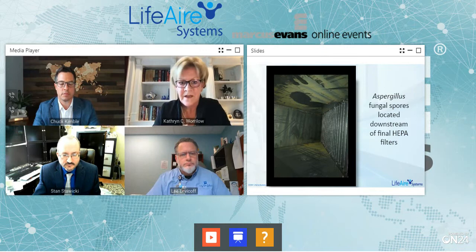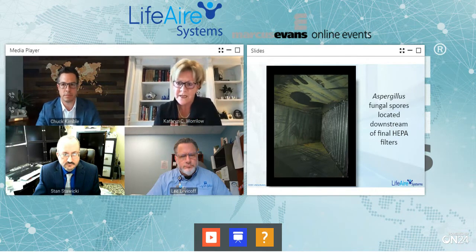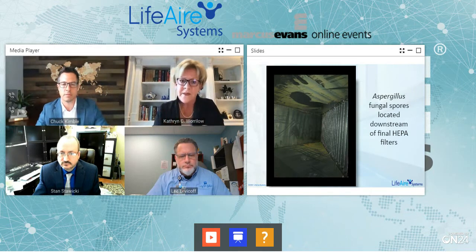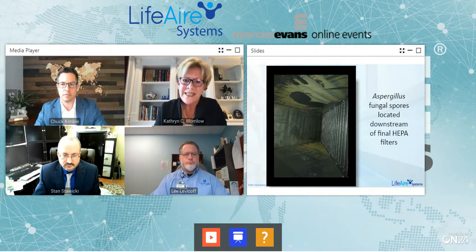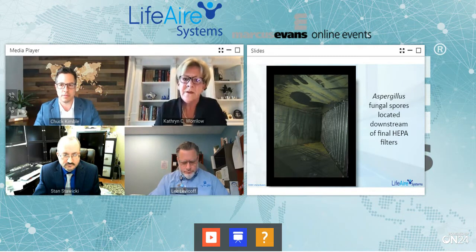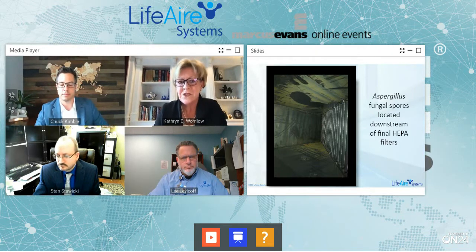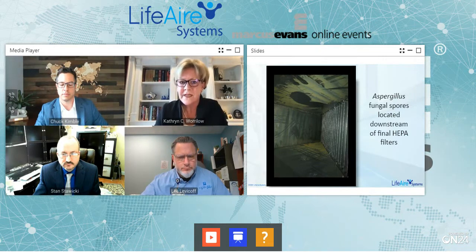Finally, on the capture method, unfortunately, we see this far too often. This is an image downstream of a HEPA filter immediately before the air enters the clinical space. And as you can see, the effervescent green glow on the ductwork, after swabbing this and sending this to micro, this is actually Aspergillus fungal spores. And Aspergillus is actually not that small. It is large enough to be captured by a HEPA, but you can have individual cells of the Aspergillus actually split off, which is what happened here, and line the ductwork. And again, this is after the HEPA filter, immediately before entering the clinical space. Aspergillus is one of the airborne fungal spores that is very much associated with patient illness in a number of healthcare settings.